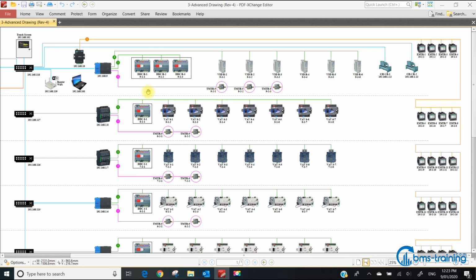And you can see here we have, on trunk 1, 3 BMS controllers. On trunk 2, we have some thermal meters. Trunk 3, we have variable speed drives. And then we've got these 2 chillers here on BACnet IP and these 4 electric meters, or this whole trunk here, on a Modbus RS485 back to a gateway here. But for the purpose of this discussion, let's just assume that all of these are connected together. So on one BACnet MSTP subnetwork, we have 1, 2, 3, 4, 5, 6, 7, 8, 9, 10, 11, 12, 13, 14, 15, 16, 17, 18 devices, all daisy chained together along the RS485.